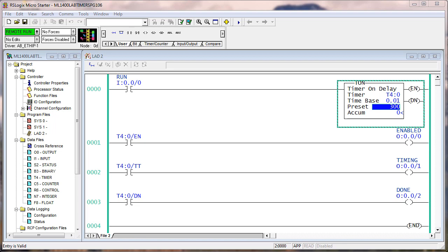You're going to see hundreds of these timer data types used in your career working on PLCs and PACs. By the way, there are no countdown timers. You only see the preset and the accumulate — the accumulate accumulates units of time, in this case hundredths of a second counting up. It's not a countdown timer where you set something at 300 and watch it go 299, 298, 297. There are other controllers where the firmware shows you the accumulate starting at 300 and counting down until it's zero, then the timer's done.